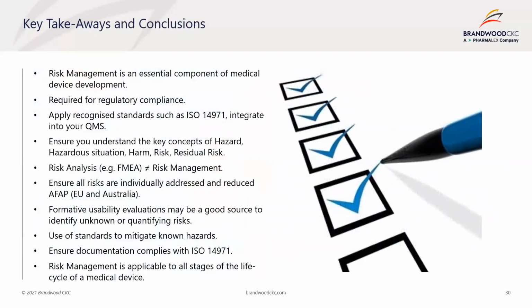So finally, some key takeaways and conclusion. Firstly, risk management is an essential component of medical device development. It is required for regulatory compliance. Ensure you apply recognized standards such as ISO 14971 and integrate it into your QMS, especially the design controls. Ensure you understand the key concepts of hazard, hazardous situation, harm, risk, residual risk, etc.